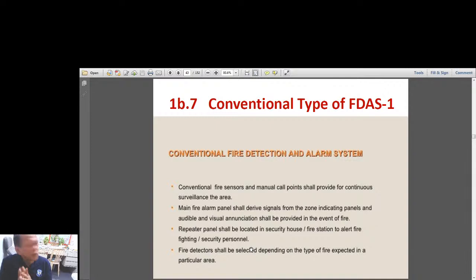Okay, so for a four-story building, which would have a maximum of 8 zones, the cost of the fire alarm control panel for the conventional would be something like 100,000. But for an addressable type, the equivalent could cost 60,000 more, so 160,000. So something like that. Of course, the addressable type is now being used for bigger buildings like malls and high-rise and so on, because it has the capacity to provide more accurate safety and protection for your occupants.